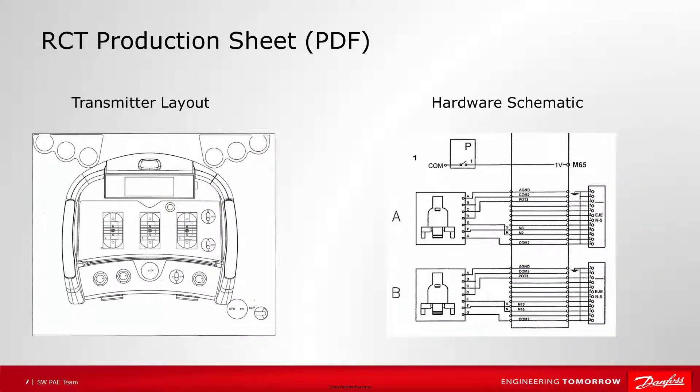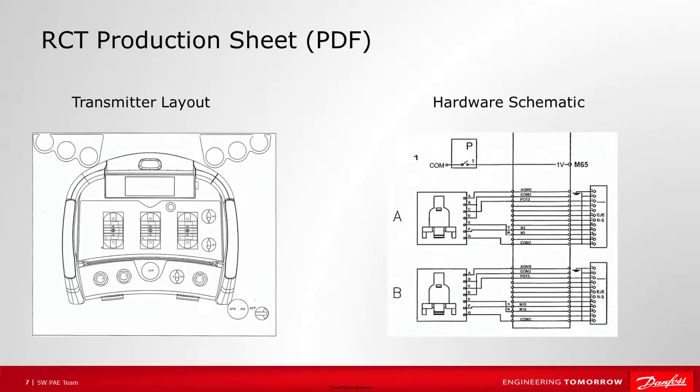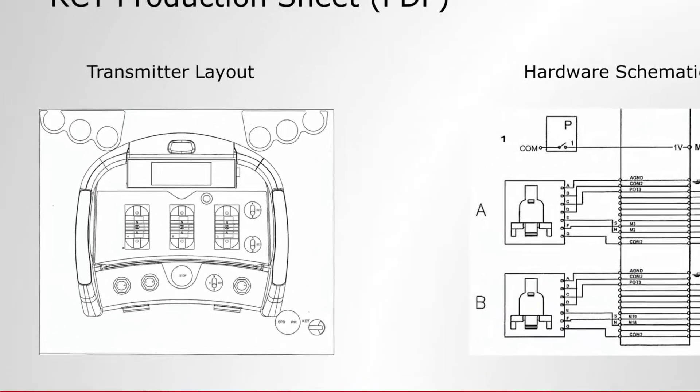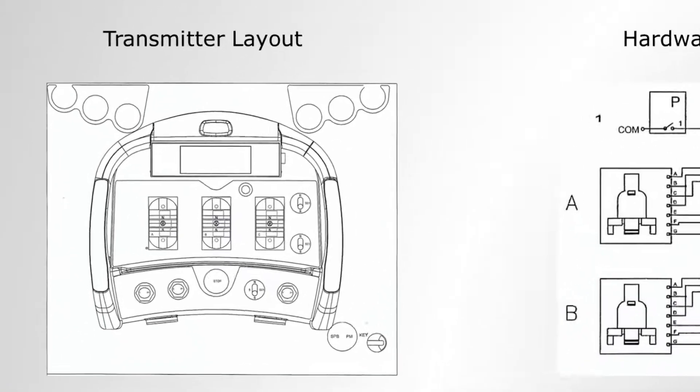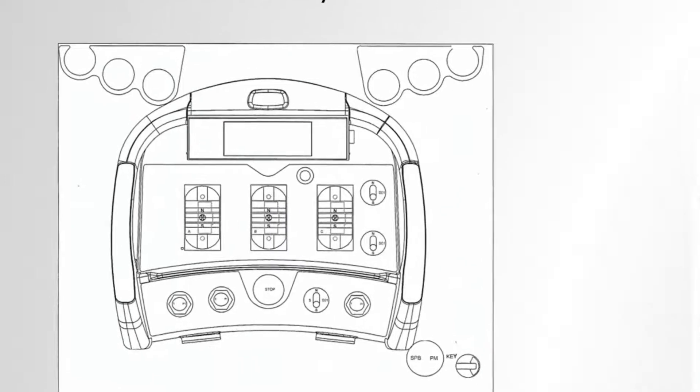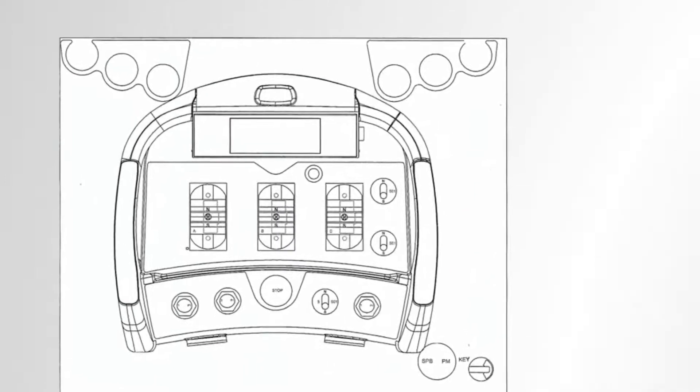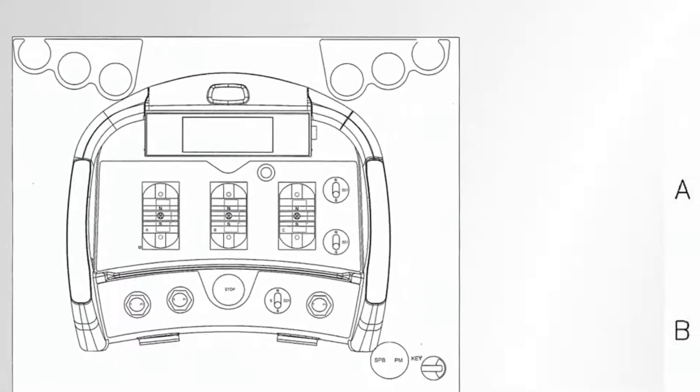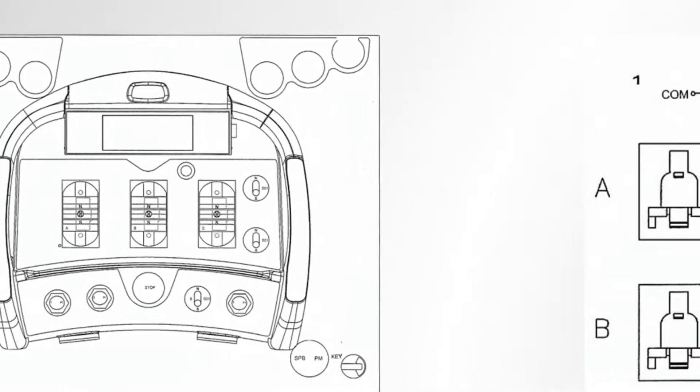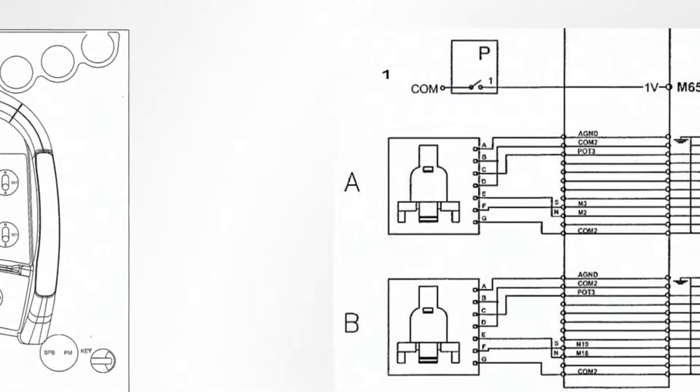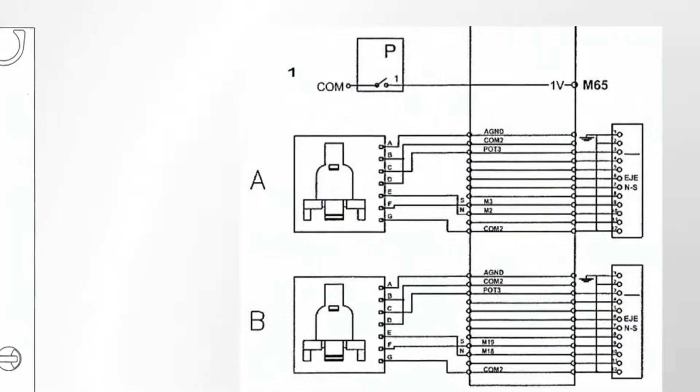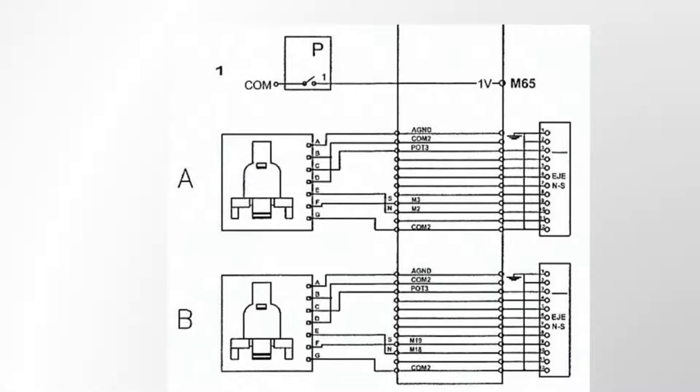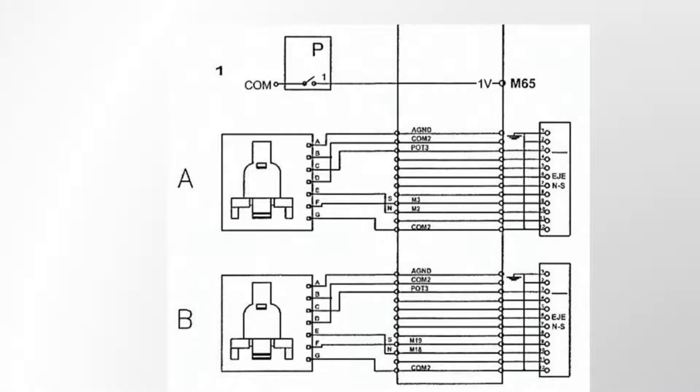The production sheet you received from Danfoss for the RCT transmitter will show the layout and have hardware schematics. My transmitter has three paddles with north and south directions. For my example, I'm going to use only paddles A and B. In the data sheet, I can see my north and south maneuver values, M2 and M3 for A, and M18 and M19 for B.